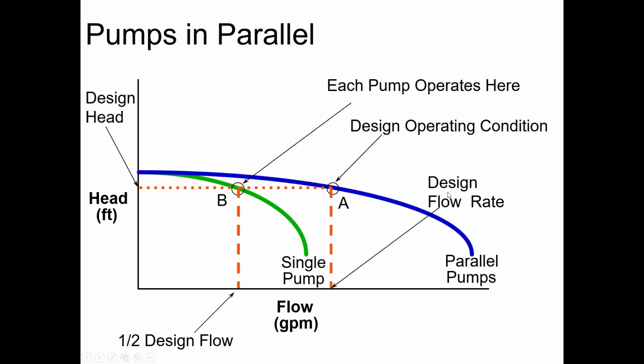But when you're doing pumps in parallel, real quickly, what we're trying to highlight here is this is my design condition right out here. So my design flow rate is this, A. But I'm picking 2 smaller pumps. And each pump will give me half of the desired flow rate, but at the necessary calculated head loss. So each pump can give me half the flow at the design head loss. And when I put them in parallel, and they're running in parallel together, they will give me double the flow, the appropriate flow rate that I was chasing after at that design head loss. So pumps in parallel, each one gives you half the flow at the total head, put them together, and they'll give you that.